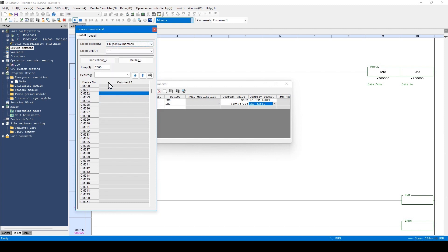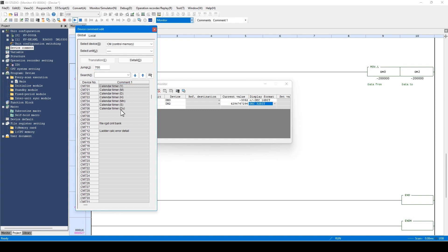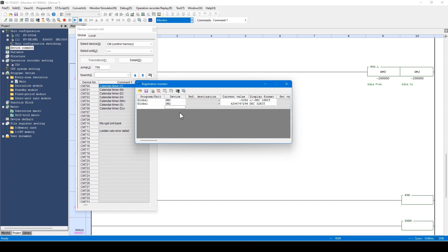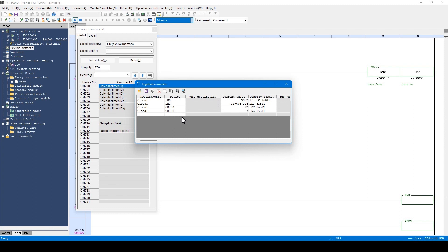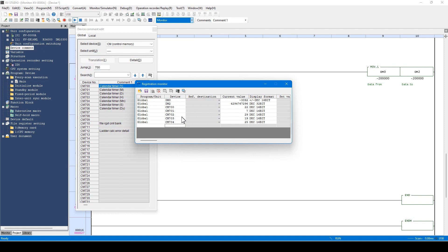Let's change the display to CM. For example, numbers after CM 700 have the PLC calendar data stored. Let's register the data after CM700 to the Registration Monitor window. Enter CM700 and press the Enter key, then register in consecutive numbers. Place a cursor on the line below CM700 and press Control + I on the keyboard. You can register devices of consecutive device numbers automatically. Now you can see that the PLC calendar data are stored. In order to use data like this, use CM.